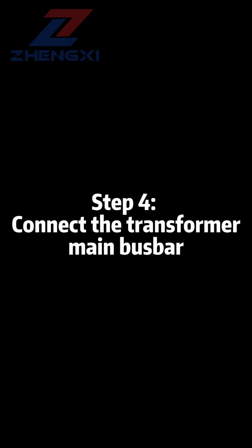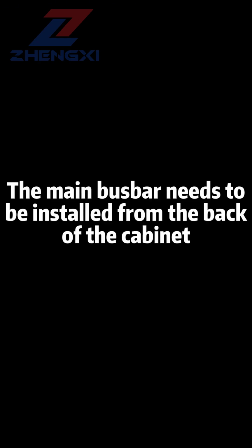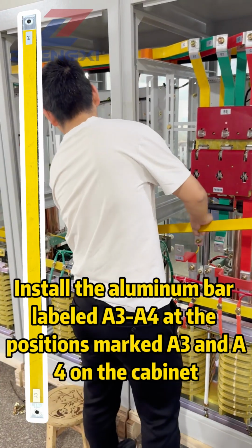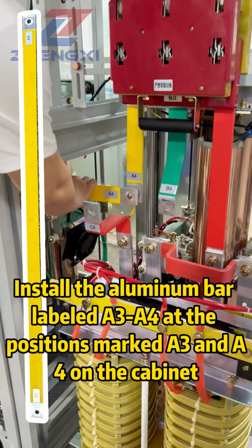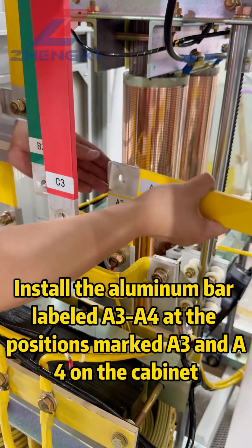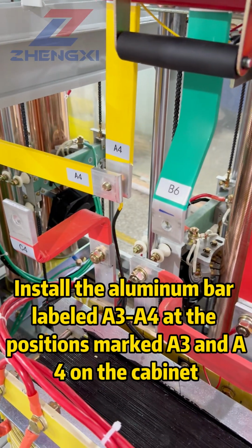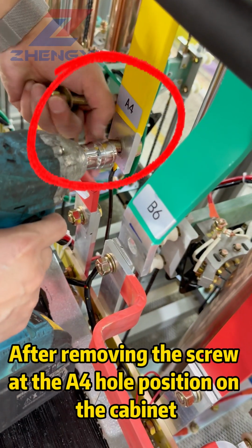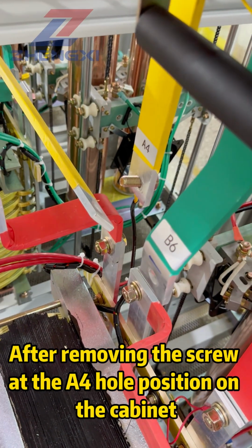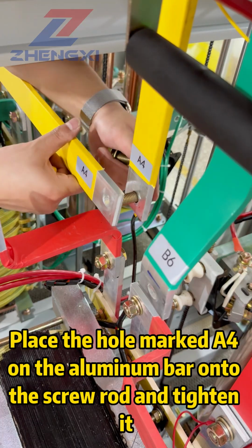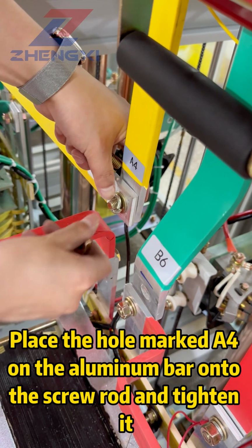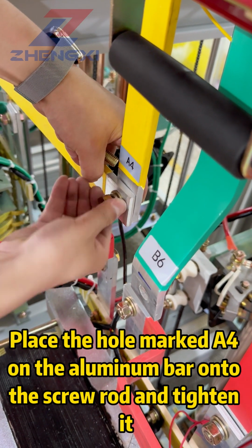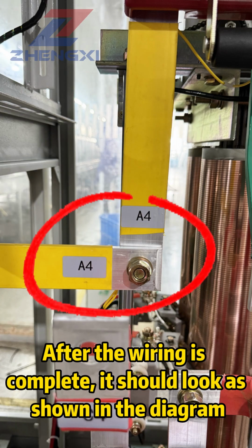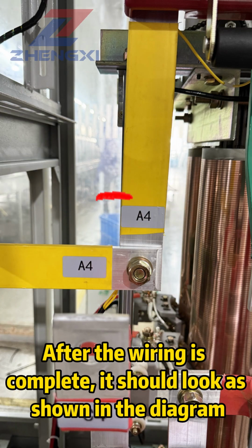Step 4. Connect the transformer. Main busbar. The main busbar needs to be installed from the back of the cabinet. Install the aluminum bar labeled A3, A4 at the positions marked A3 and A4 on the cabinet. After removing the screw at the A4 hole position on the cabinet, place the hole marked A4 on the aluminum bar onto the screw rod and tighten it. After the wiring is complete, it should look as shown in the diagram.